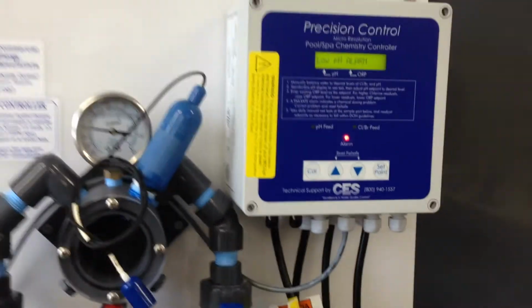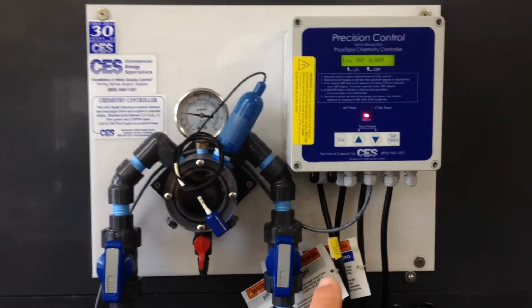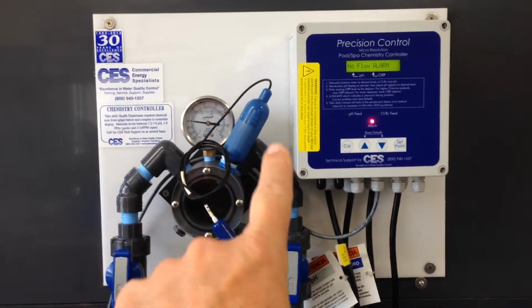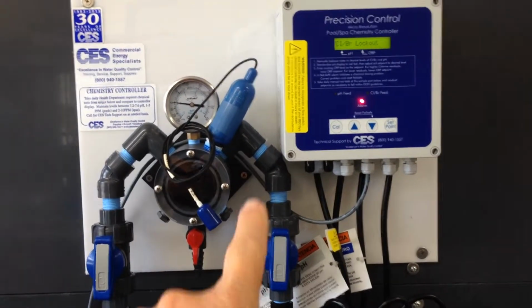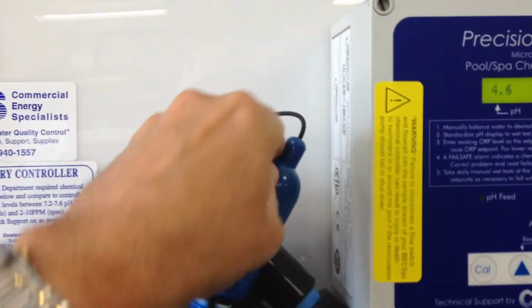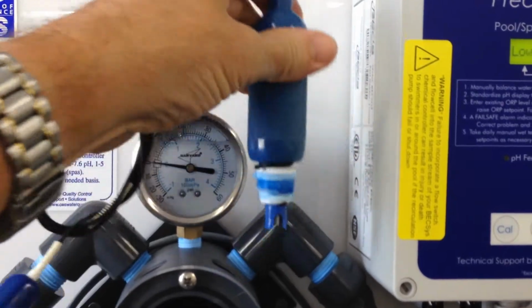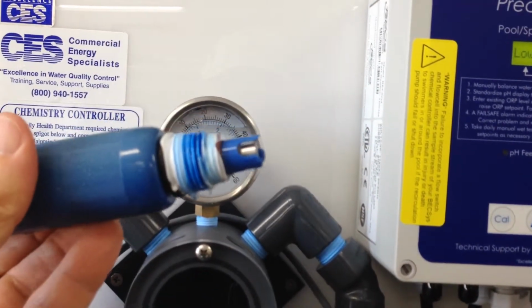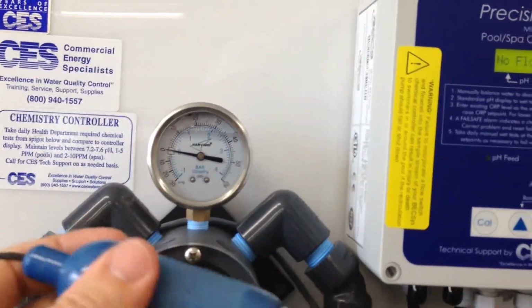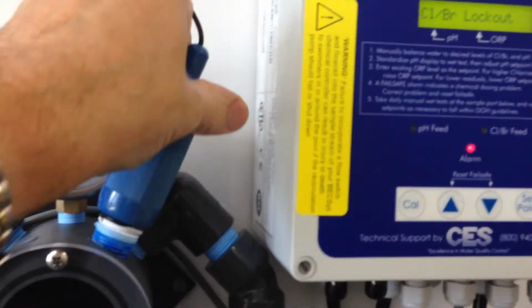So the way it starts is you have the water flow in and out, as we discussed, inside one, outside the other. You take the two sensors, and you screw them in. What you do is you normally put two wraps of tape, you shake them down, and put them in position. The blue one goes into the blue port right there, and the white one, or the gray one, is for pH, goes into the gray port there.